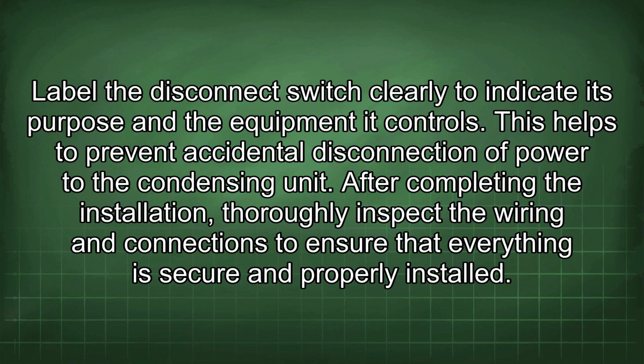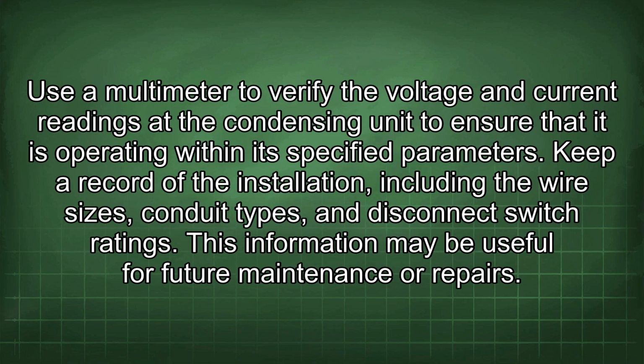After completing the installation, thoroughly inspect the wiring and connections to ensure that everything is secure and properly installed. Use a multimeter to verify the voltage and current readings at the condensing unit to ensure that it is operating within its specified parameters. Keep a record of the installation, including the wire sizes, conduit types, and disconnect switch ratings. This information may be useful for future maintenance or repairs.